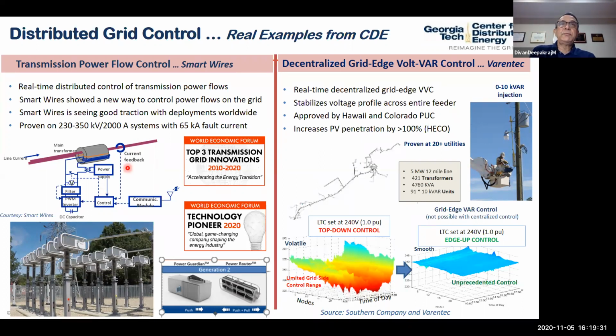It's taken a long time. I think we demonstrated the first devices at 350 kV probably in the 2008-2009 timeframe. They are now, this year, extremely successful, doing very well, and you can see some of the awards they've been able to get. This shows the ability, at transmission line levels, to inject dynamic impedances into the line and control power flows, doing power routing capability, all in a distributed manner. So this was a very good validation of distributed grid control on the transmission side.